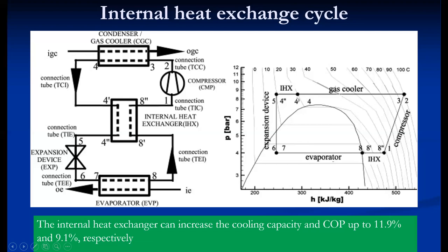Four to four-dash remains the same, assuming no heat leak or heat gain in this piping. Four-dash to four-double-dash is where the heat is exchanged with the other fluid. This is the hot line and this is the cold line. This particular line is the high pressure gas line — not a liquid line as in conventional systems. This high pressure gas line cools the low pressure gas line coming out from the evaporator. So a temperature drop happens in the gas cooling line, that is four-dash to four-double-dash.